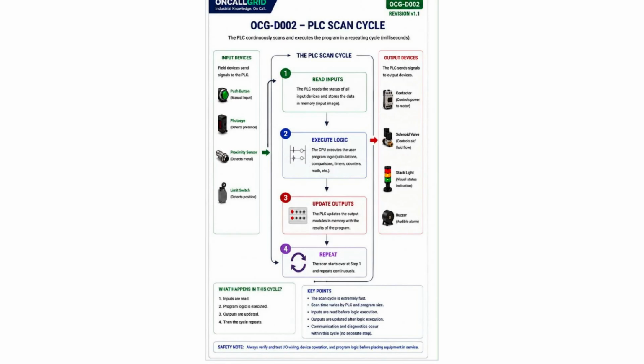Same idea on the output side. If the PLC's output LED is lit, but the contactor never actually pulls in, don't replace the PLC. Check the coil voltage, look for a blown fuse, check the overload relay, look for a broken wire or a failed coil. The PLC already did its job. It energized the output. Something downstream just isn't responding.